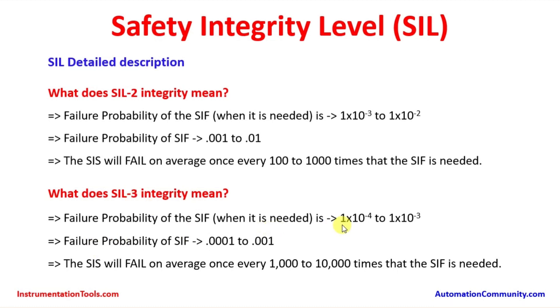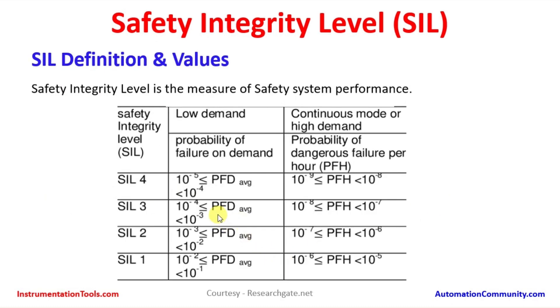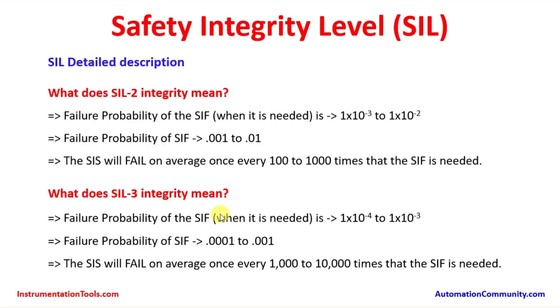For SIL 3 integrity, the range is 1×10⁻⁴ to 1×10⁻³, as shown in the table. The failure probability is 0.0001 to 0.001. The SIS will fail on average once every 1000 to 10,000 times — meaning for every 1000 to 10,000 demands, there is a probability of one failure. That is known as SIL 3.